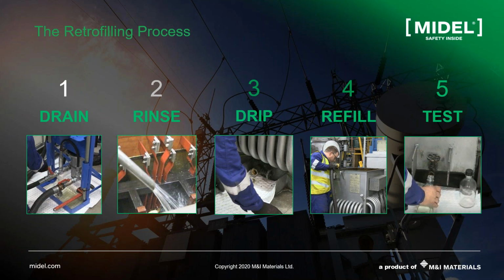And then the fourth step is refilling. Of course, we refill through a filtration machine with an inline heater, which increases the temperature of the liquid and aids in removing air bubbles, preventing them from being trapped within the transformer. Once we have done steps 1, 2, 3, and 4, and the transformer is filled and settled, we do testing. We take samples from the transformer and measure the breakdown voltage and other parameters to make sure that this is now a successful retrofit. These are the 5 basic steps of a retrofit.